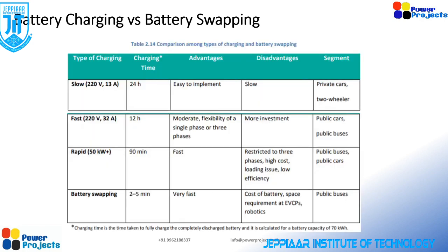So even with rapid charging, with the batteries which are available now, with a 1C battery you need to wait at least 1 hour for charging. That's not a constraint from the charger, but a constraint from the battery. As we discussed yesterday, if we increase the C rating of the battery, that means instead of 1C, if we go with a 2C or 3C or a 4C, the cost of the battery will further increase.